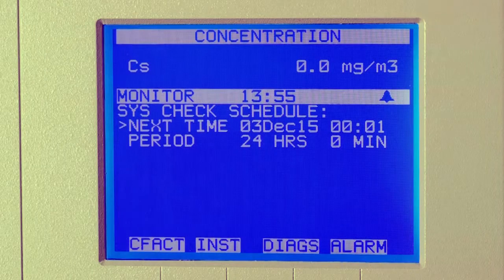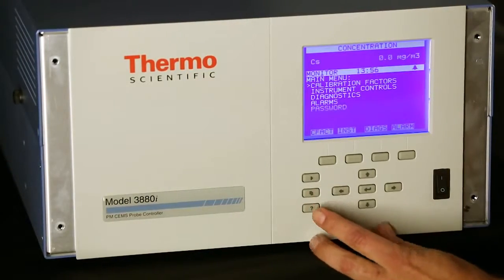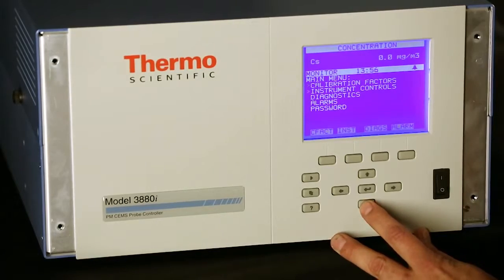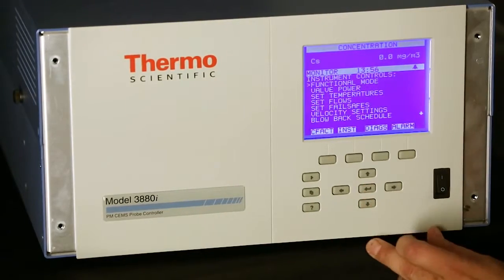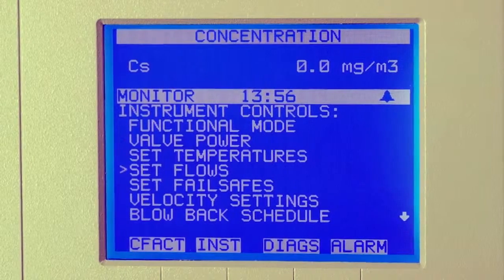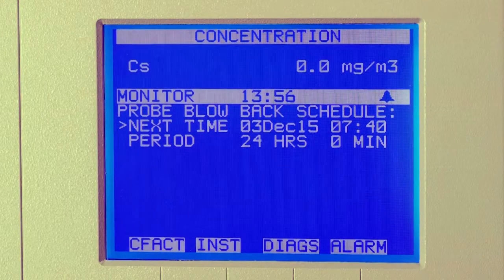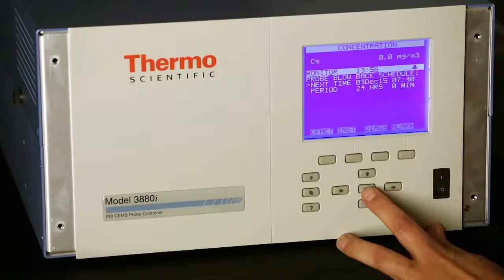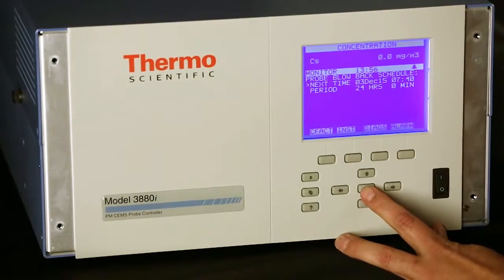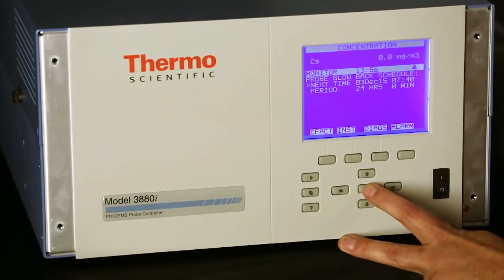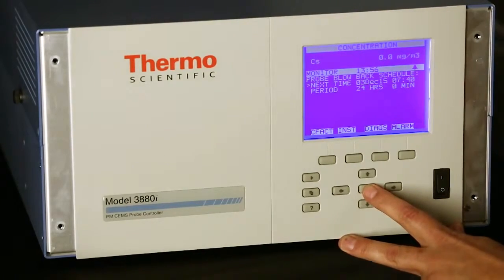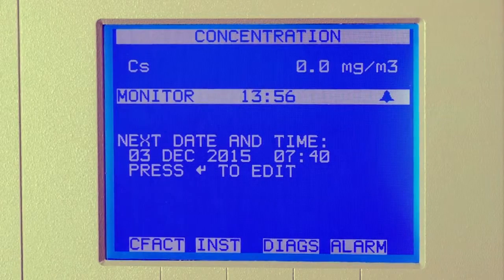From the run screen, go back to the menu, instrument controls, and hit enter. Scroll down to blowback schedule. The last time it started was at 7:40. Hit enter to set up the blowback schedule. The optimum setup time is one o'clock in the morning. Go into the next date and press enter to edit.